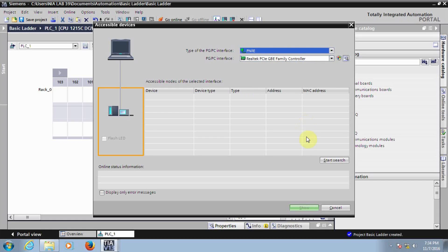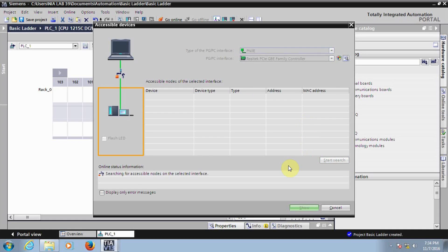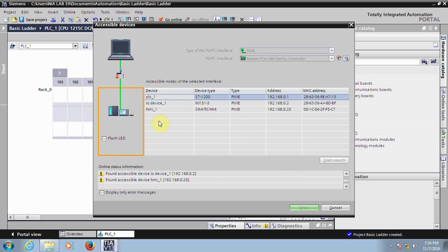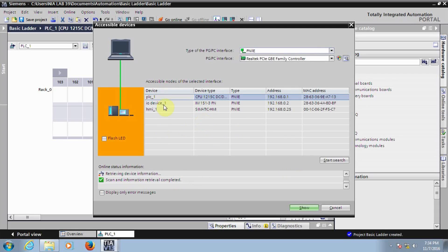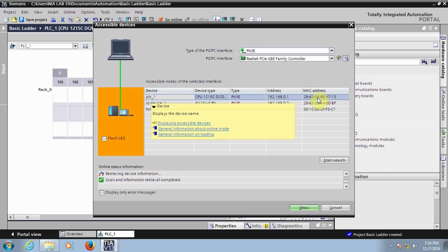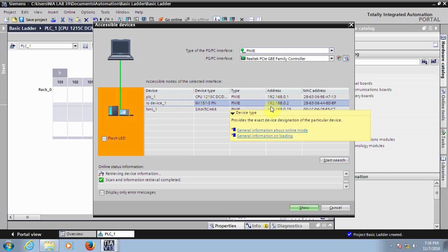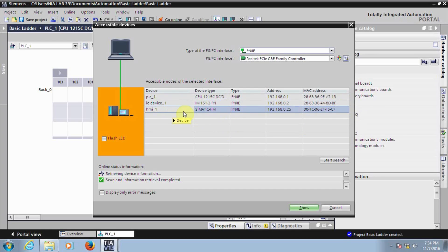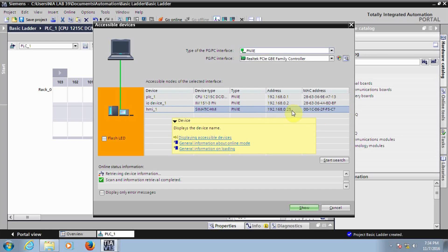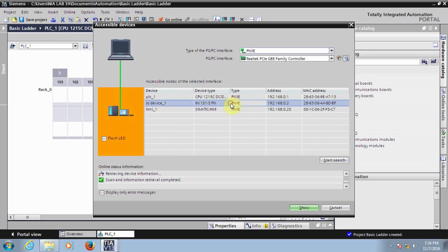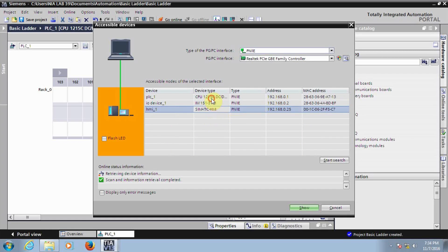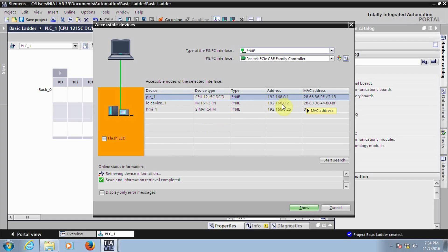This is a LAN driver, so click on Start Search. It is searching for devices connected to the network. I have connected a PLC and you can see its IP: 192.168.0.1 and the MAC address. You can also see the remote station IM151-3PN and its IP, as well as the HMI and its IP address. Later we will see the configuration of the remote station and HMI, but first we need to configure the PLC.